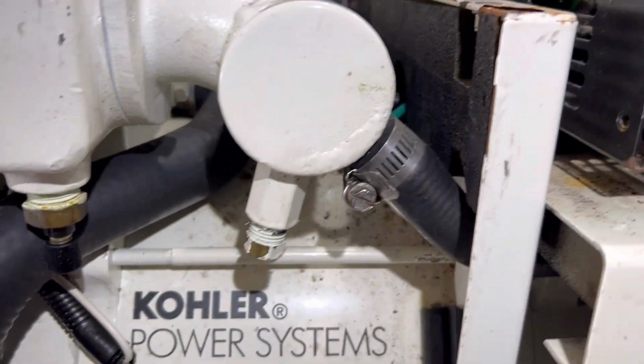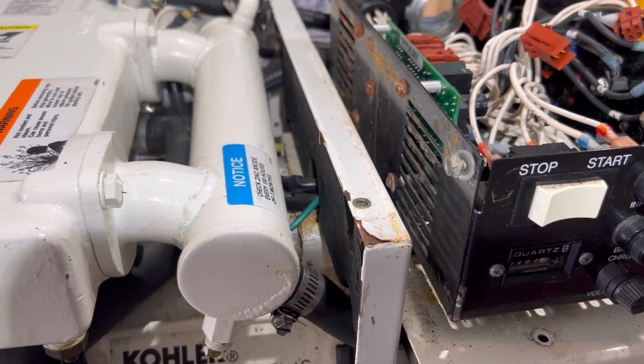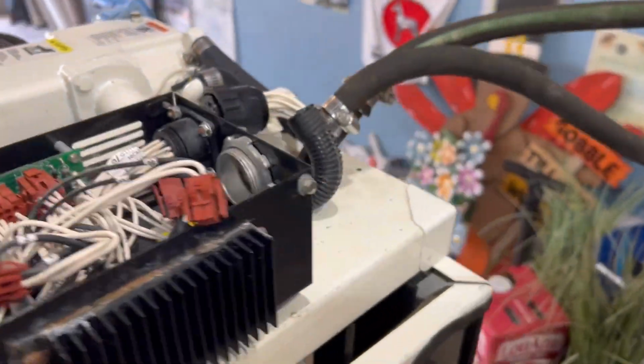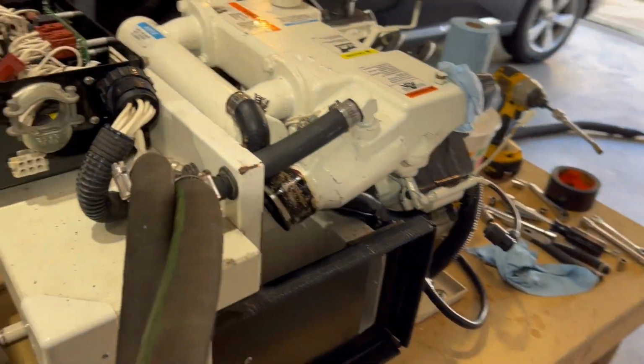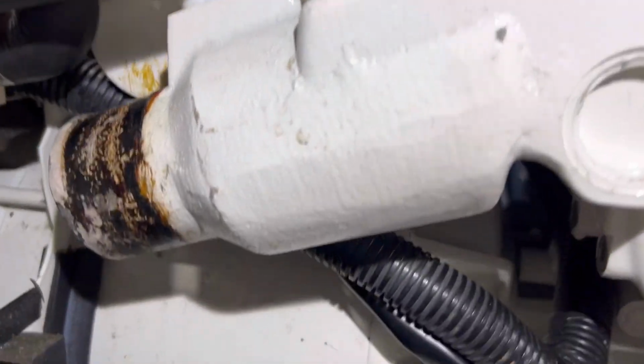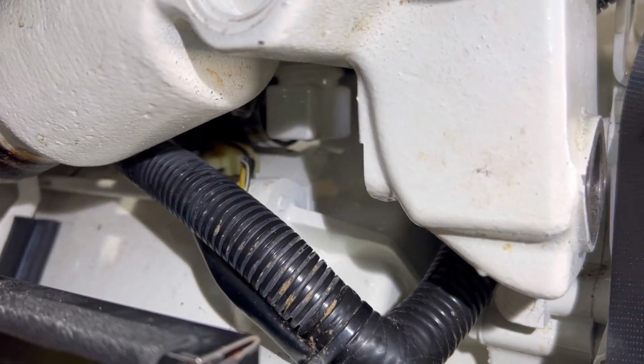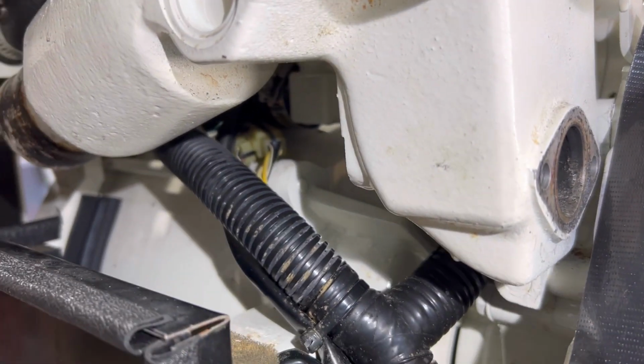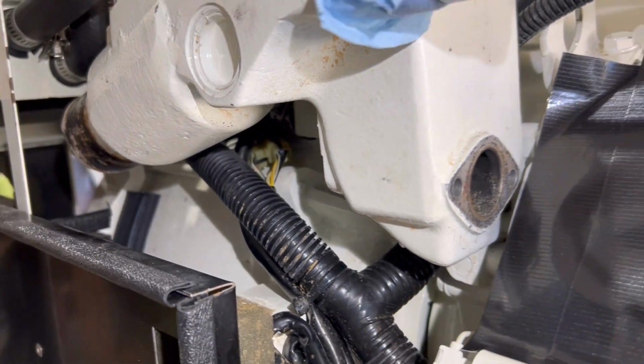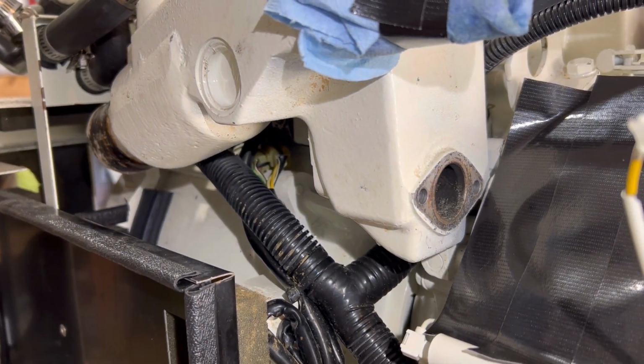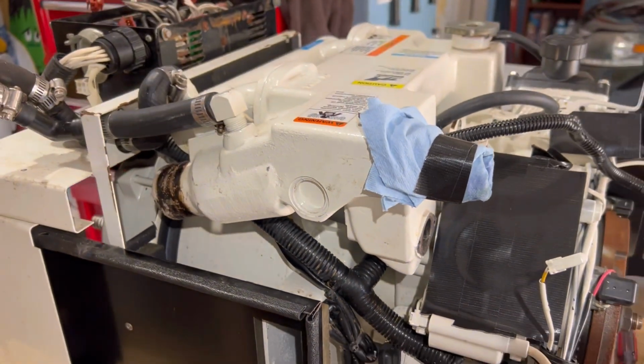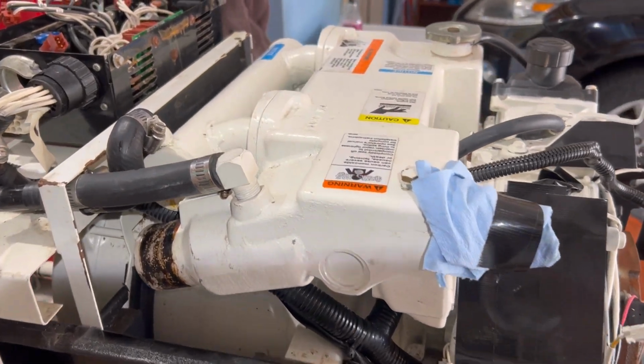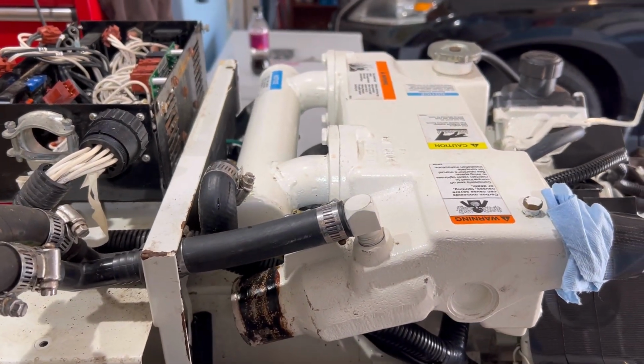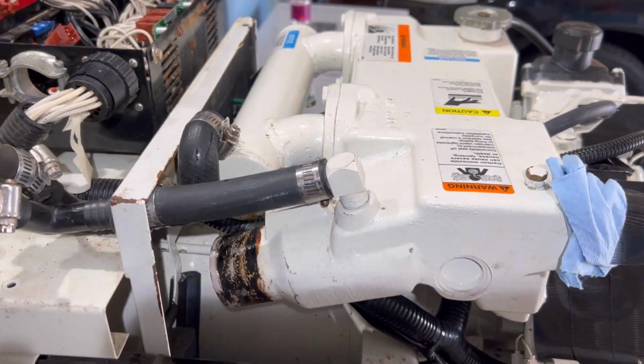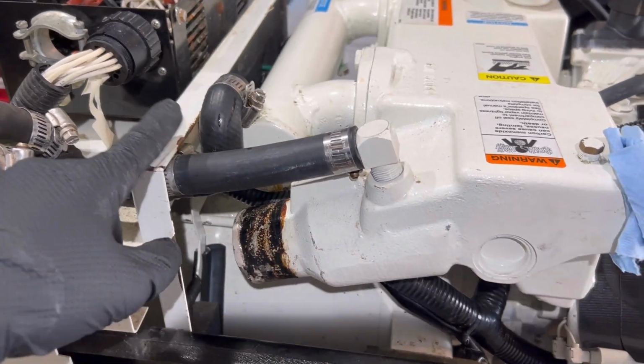There are some additional wires coming through the opening here, through the sound shield, and over on the forward side of the generator is where those connections are made. You can see the off-color white connections up inside. To get to these, it's going to be beneficial to take off the exhaust manifold as well as the heat exchanger. So I'm going to disconnect these two hoses here.